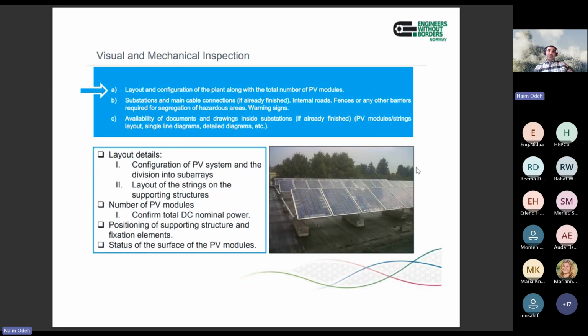So about the layout of the system, what we check when inspecting the layout is the configuration of the PV system, the layout of strings, the supporting system, the structure, and so on. Also we check the number of modules - not per string in depth, but in the drawings you have the number of modules shown in each row, so I mean checking the number of modules in each row.